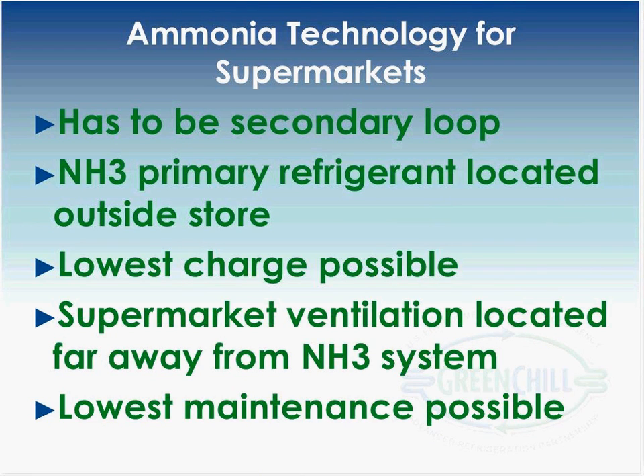As Caleb was indicating, in these applications the ammonia would have to be the primary loop refrigerant because it is a B2 refrigerant, and therefore it needs to be contained remotely from any occupied space. By doing this, we would be able to obtain the lowest charge possible.